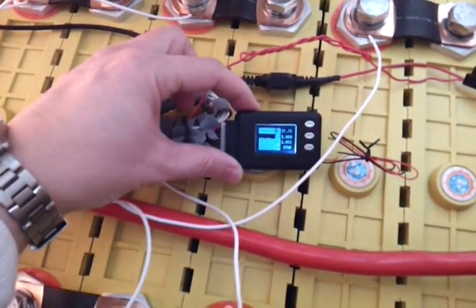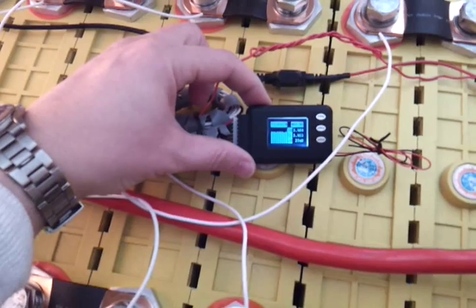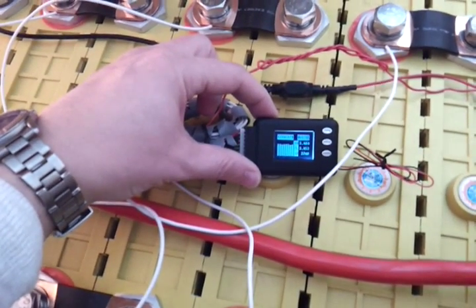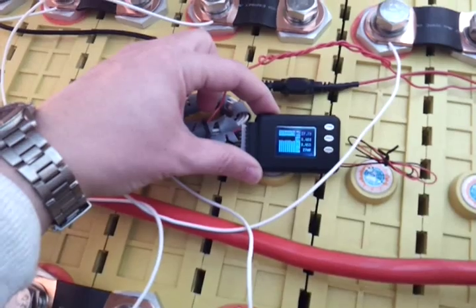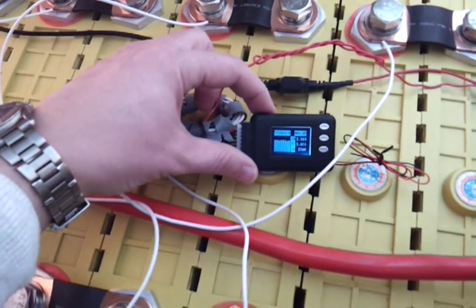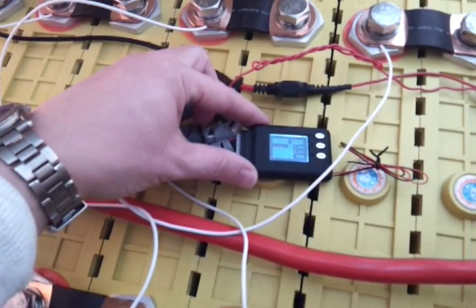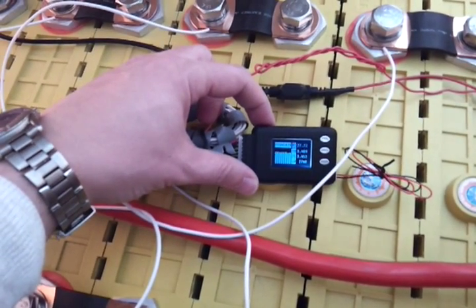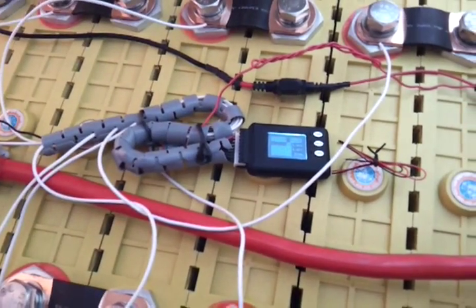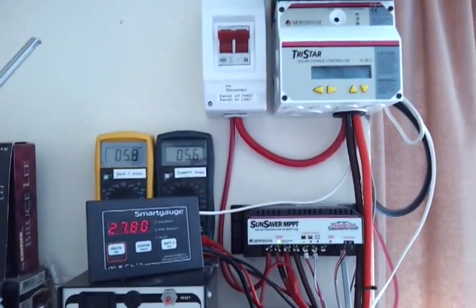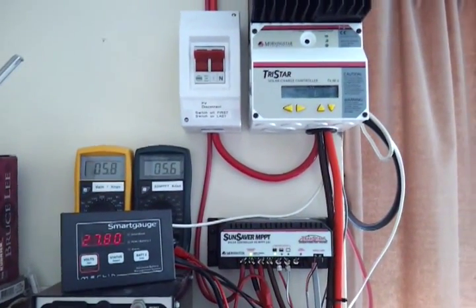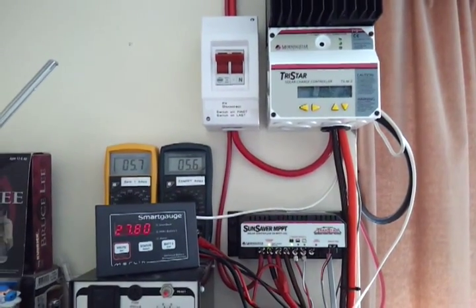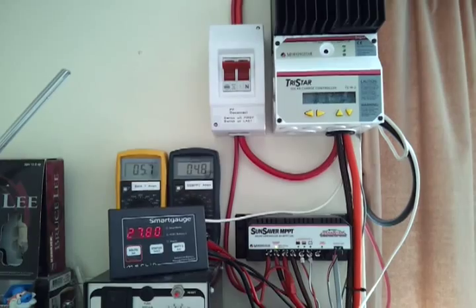The cell log is showing a good balance even at this charge rate - only 27 millivolts difference between the highest cell and the lowest cell. Getting quite near the 28 volt limit where the charger should go into its constant voltage mode. So we should see the charger start to wind down in a few minutes and then drop down to its float level after 10 minutes.